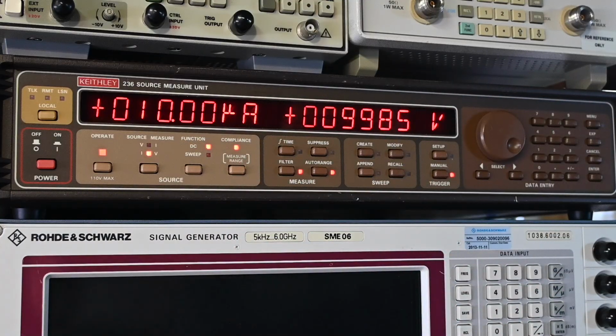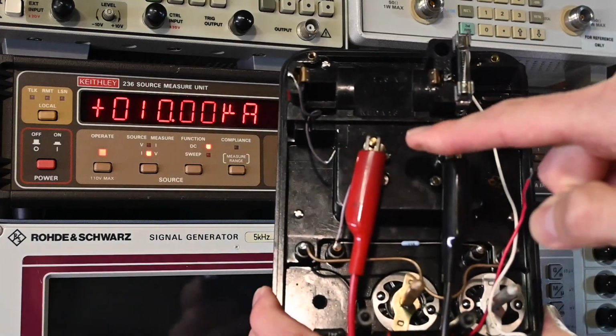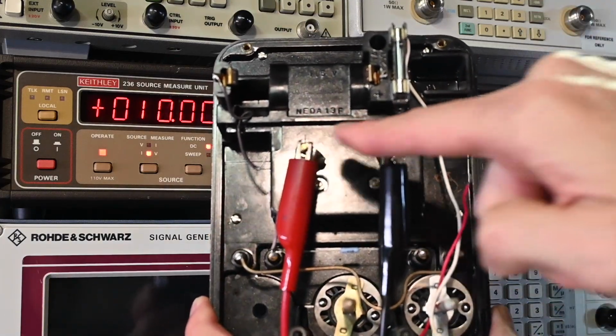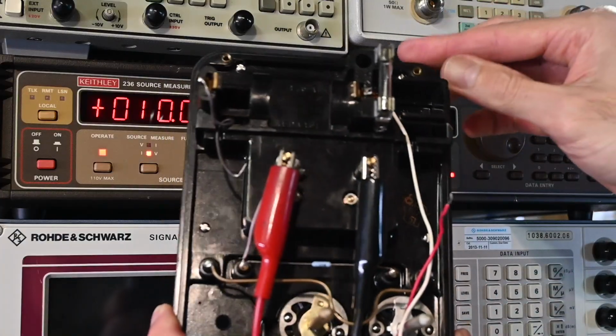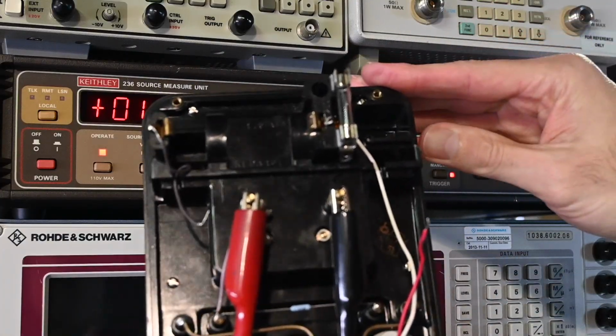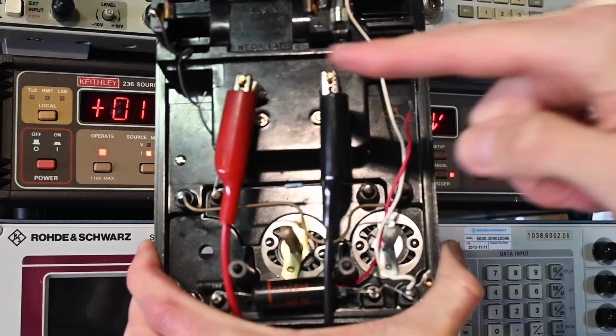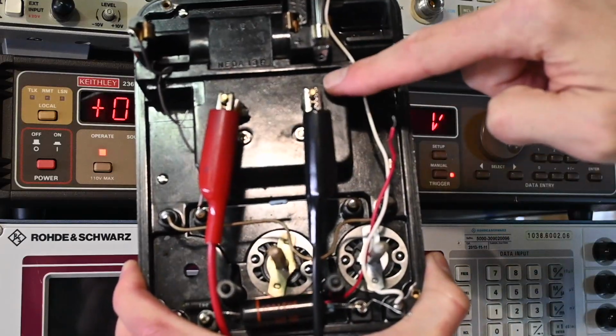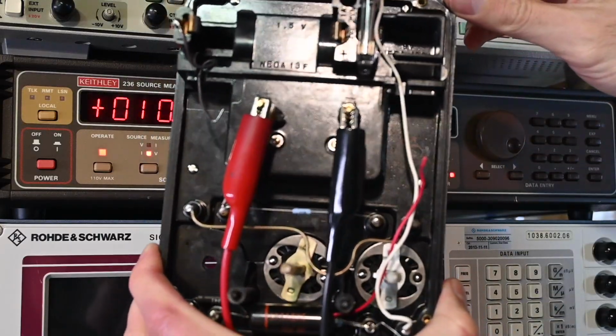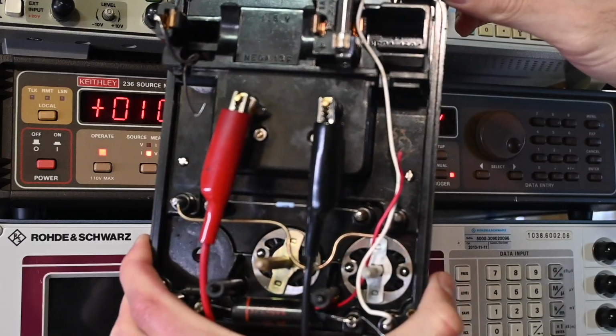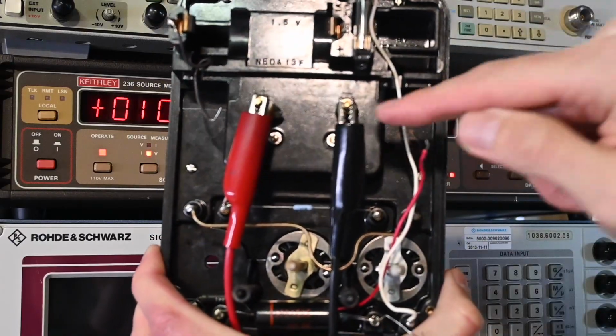All right, so I'm going to connect this right here to the meter, and I have to do this test before the main circuit board is installed, because once the main board is installed, you don't have access to these meter terminals without other circuitry that would be interfering in here. This is the only time you can get directly onto the meter with no other circuitry in here. I'm just going to set this out of the way for a moment, but again, this is how it's connected. Positive on this side, negative here. Polarity marks are up on the top right there. You can see, I think, the glare off of there, but anyway, there are polarity markings in the casting right in there.